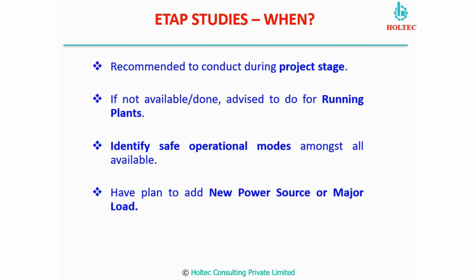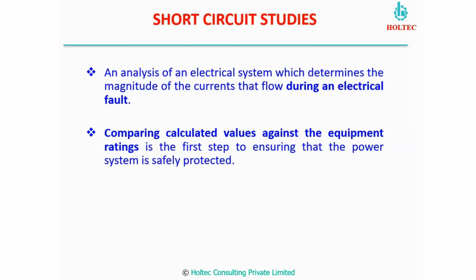It is also recommended, if you are adding a new source or major loads, that you conduct these short circuit studies. What are short circuit studies? It is an analysis of an electrical system to identify the magnitude of the fault current during any electrical fault we create in the system.